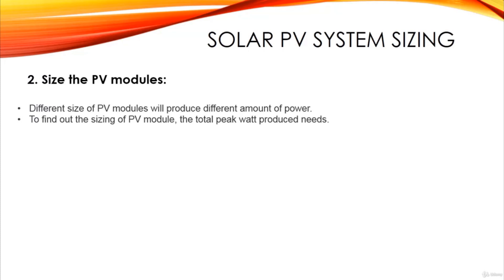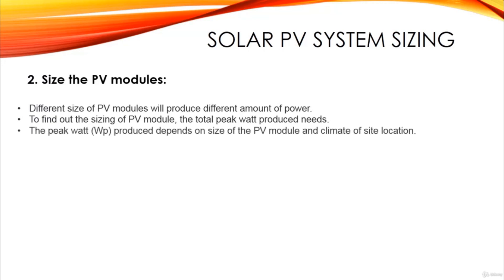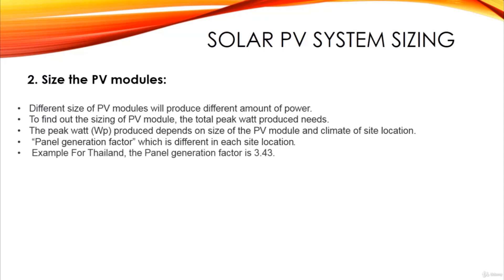In order to get the total peak watt, we will use an equation. The watt peak (Wp) produced depends on the size of the PV module and the climate of the site location. There is an important factor called the panel generation factor, which is different for each site location. For our example using Thailand, the panel generation factor is 3.43.